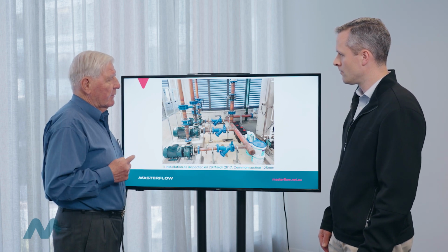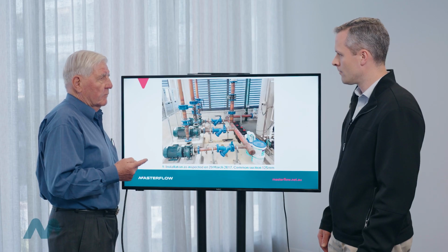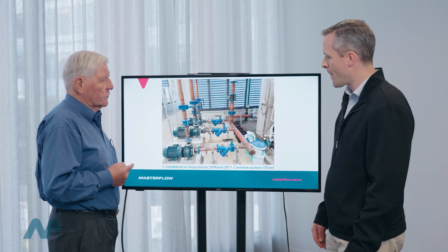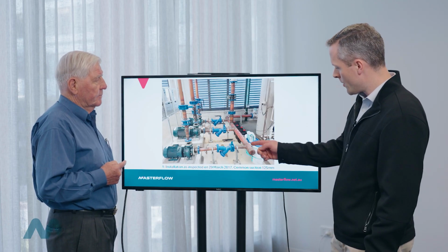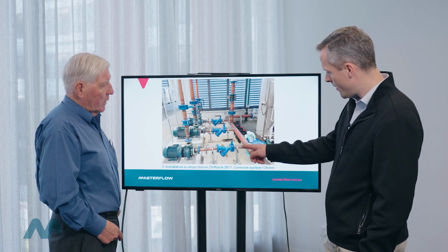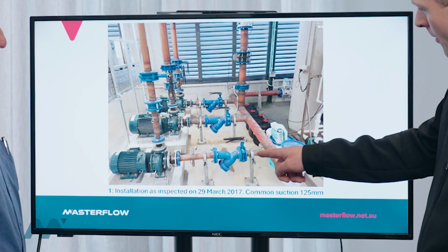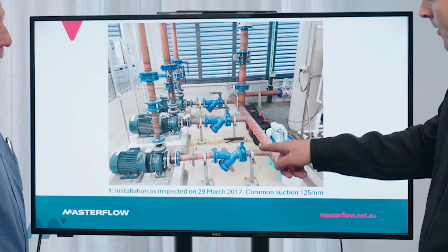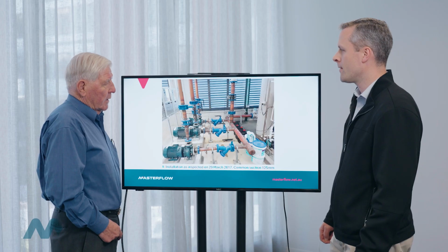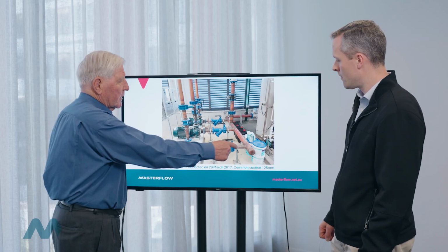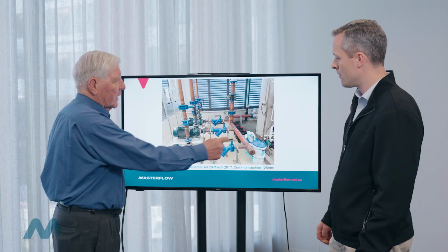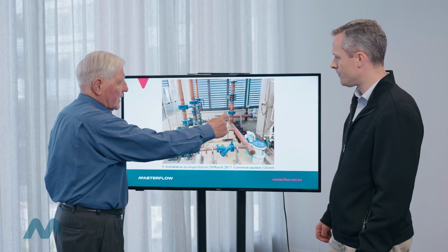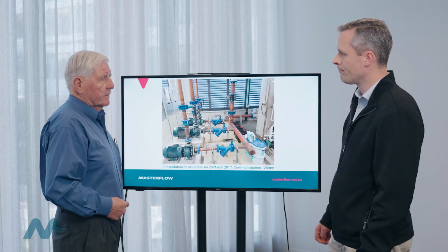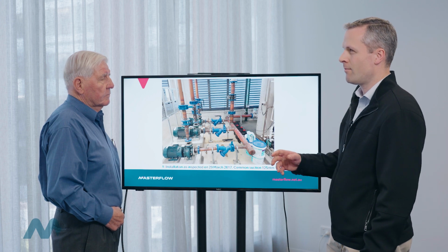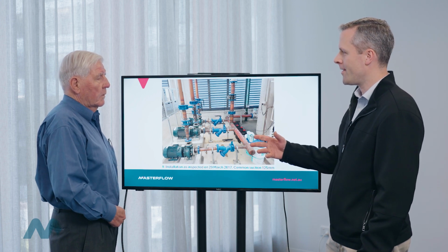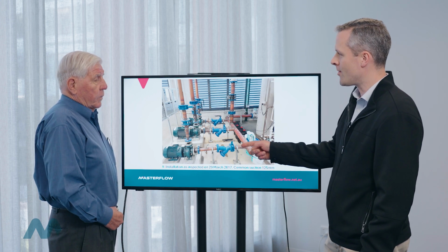Can you bleed the air out of the system, and is it done reasonably frequently to make sure there's no trapped air in the suction line? I can see on the pipework, Keith, there is a manual ball valve here on each branch. Is that sufficient to get rid of the air? No. I mean, it's in the wrong place to get rid of the air in this larger pipe. What you need is, at the highest point of that suction line, to have a bleed valve to get the air out. That's because air takes the easiest path, is it? And going down a branch is not?